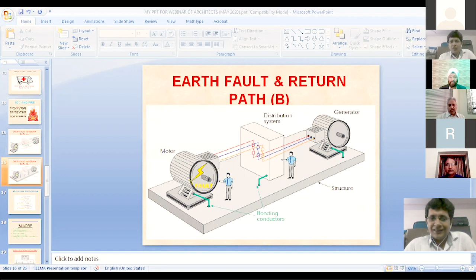Earthing itself has six factors you have to consider. First, measurement of resistivity. You have to keep in mind the short circuit current that may happen in your vicinity in that project. What is the area of the earthing conductor you are going to choose? What is the current density you have to take care of? Resistance comes last, along with human safety in terms of tolerable touch and step potential, and ground potential rise that happens because of the fault.